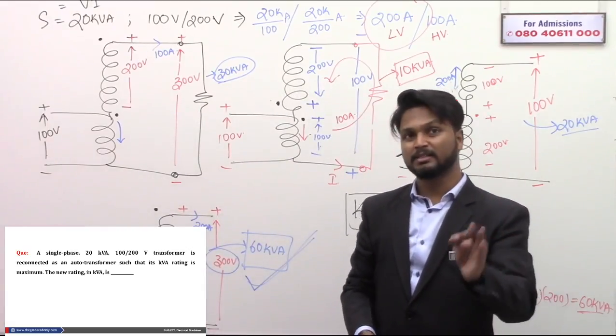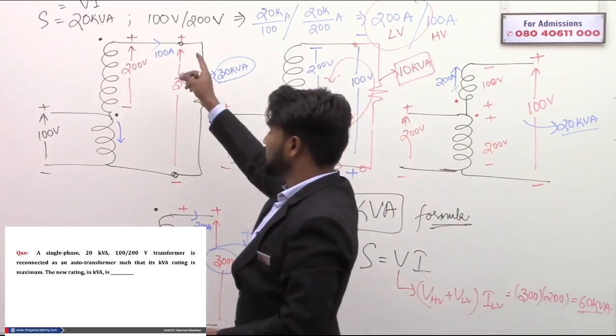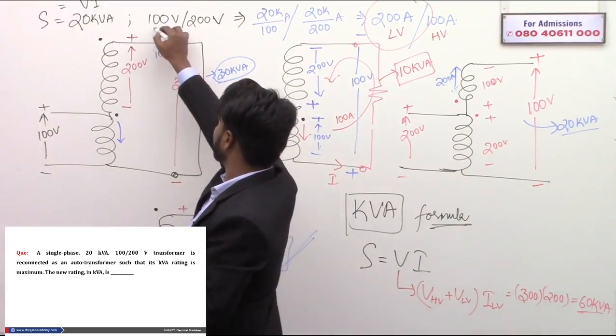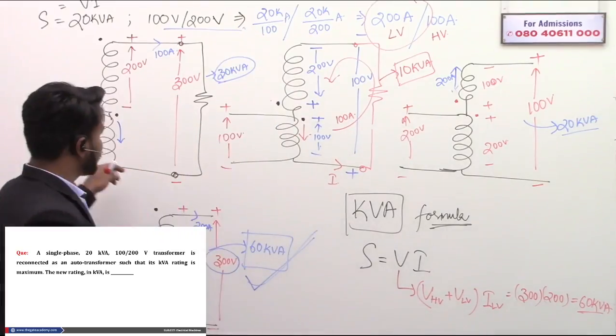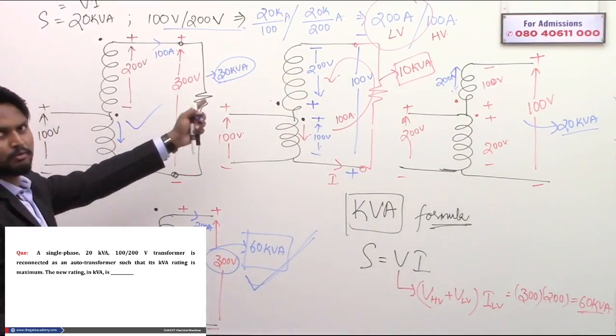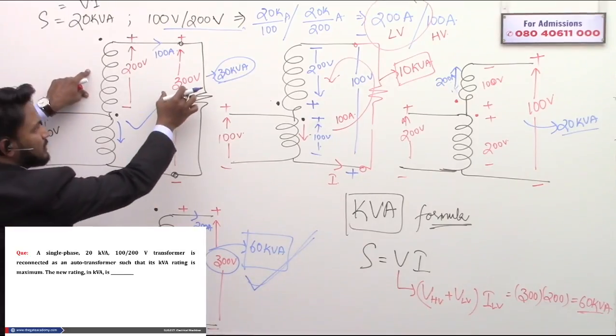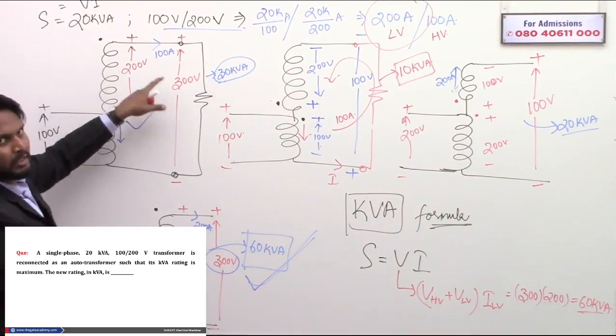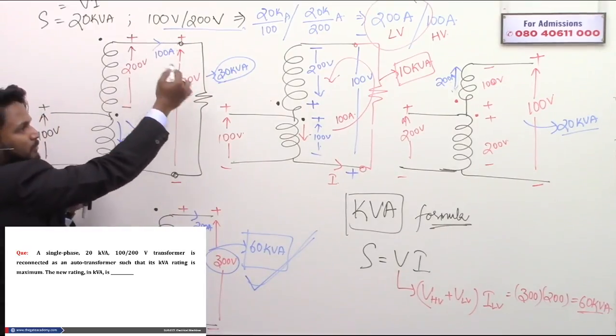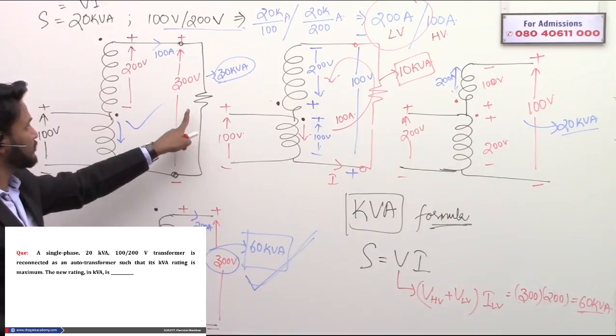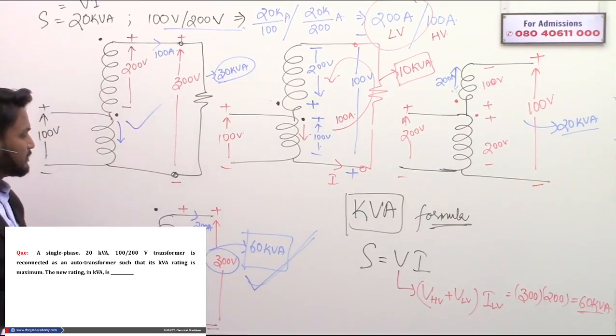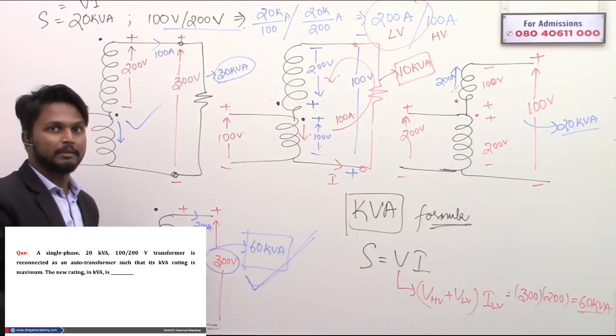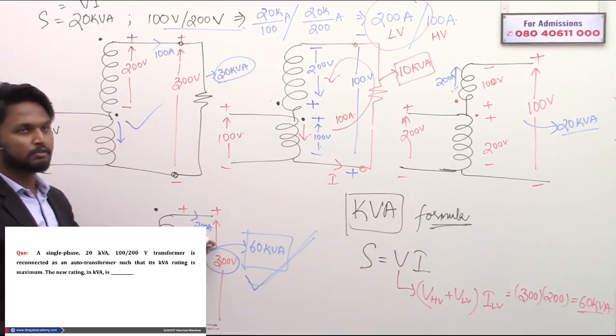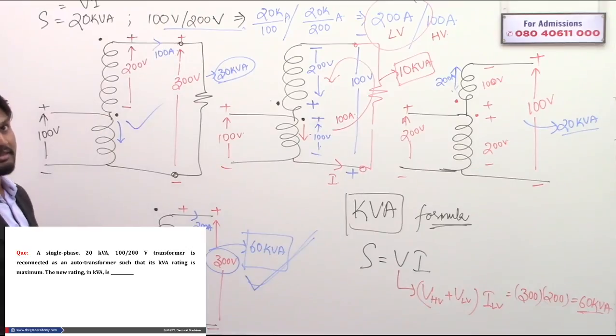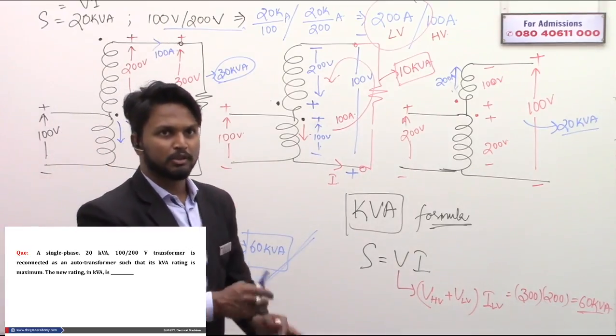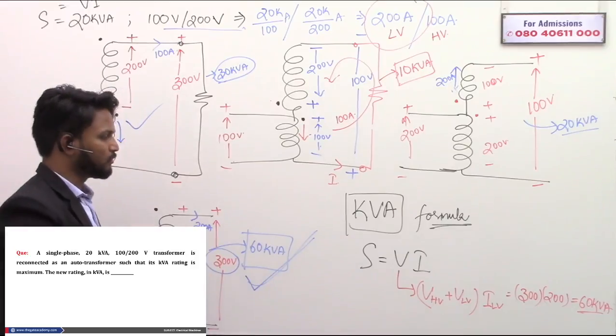Provided that the maximum kVA rating obtainable from a two winding transformer is asked - many times the configuration is given and they ask you to find the kVA. Even that is simple: find the output voltage, and the maximum current that can be drawn from the winding associated with the load. Here the winding associated with the load is HV, there it's LV. The current that can be drawn here is 200 amperes, and from this one is 100 amperes. So depending on the winding and the voltage, you obtain the kVA rating.